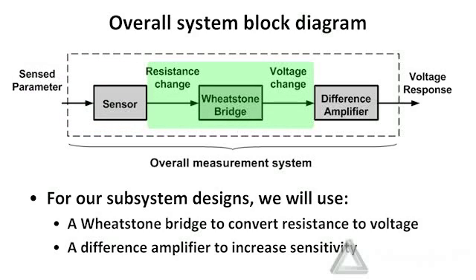In the next stage, we take that resistance change and convert it to a voltage. What we're going to use for that stage is a Wheatstone bridge. One of the primary reasons for using it is that you can modify this bridge circuit to compensate for outside influences — a key challenge in measurement system design is making the output respond only to what you're trying to measure.